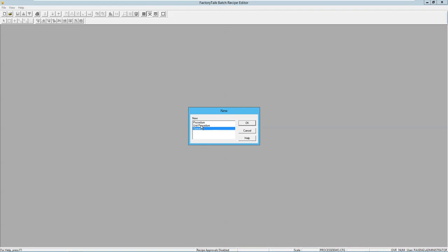A unit procedure contains operations, so that has a sequence step of operations, but again those operations can only be on one unit. So maybe I split our recipe up into different operations on a particular premixer, adding material, mixing material for example. The unit procedure would have those 2 steps one after the other on the premixer.